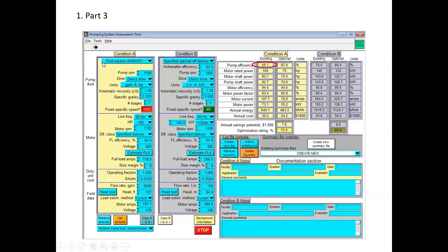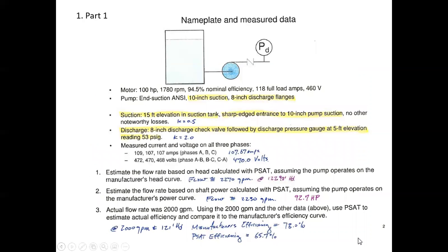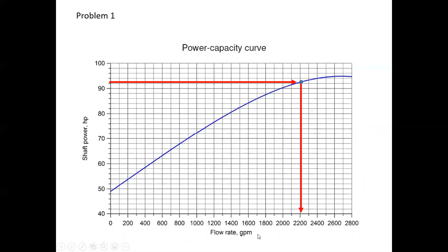Okay, that's pump 2, so we go back to, okay, so this is where I wrote the numbers down. So we're at 2000 GPM at 121 feet of head. Manufacturer's efficiency is 78, and the PSAT efficiency is 65.7. So looks like we're degraded. It could be some issues with the impeller. Something's not quite right. Wear rings could have opened up. We may have some leakage, recirculation, whatever, but it would be cause to maybe open this pump up next time we had an opportunity and take a look at it, see if we can figure out exactly what's wrong with it. Okay, so that's number 1.